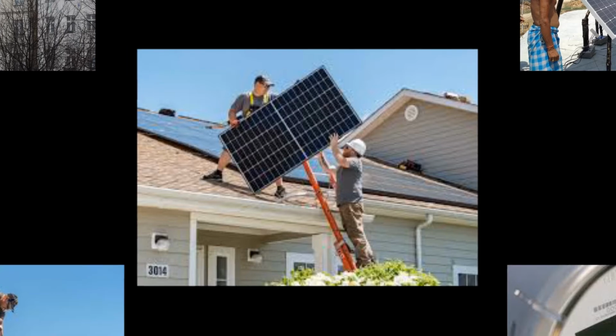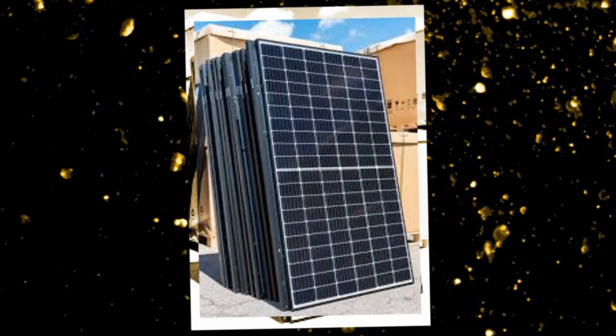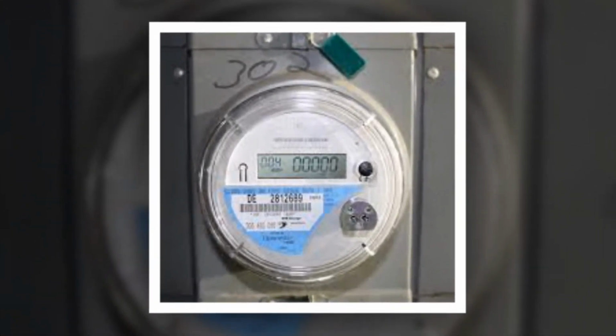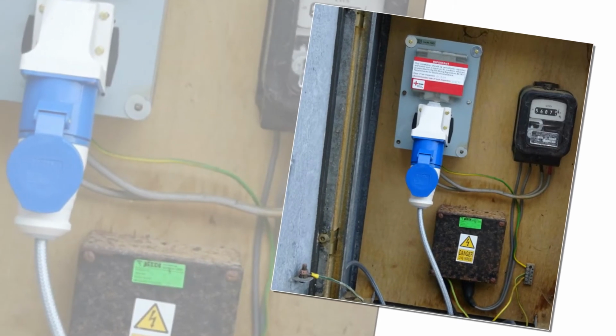Procedure and guidelines for installation of net meter in Haryana. 1. The eligible consumer shall make an application in the prescribed form to the SDO, OP, of the area, along with an application processing fee of Rs 1,000, for seeking permission for installation of a rooftop solar system in his premises under net metering arrangement. 2. An acknowledgement in lieu of receipt of application is to be given to the consumer on the same day by the Sub-Division Office. 3. Site verification is carried out by the SDO, OP, concerned within 3 days of receipt of application for net metering.